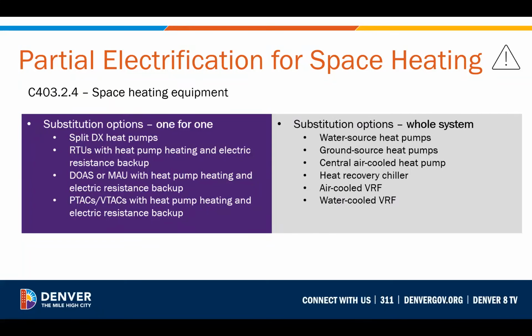So when looking to comply with this, we wanted to make sure there were options, to go over the options that you can comply with. So we have substitution options, either that one-for-one quick replacement or more whole system changes where you would design a different system due to this. So one-for-one replacement, right? If you have like a furnace with split AC, you could replace that with a split DX heat pump with a fan coil. So very similar, but you're using that heat pump instead of the gas or electric resistance heating.